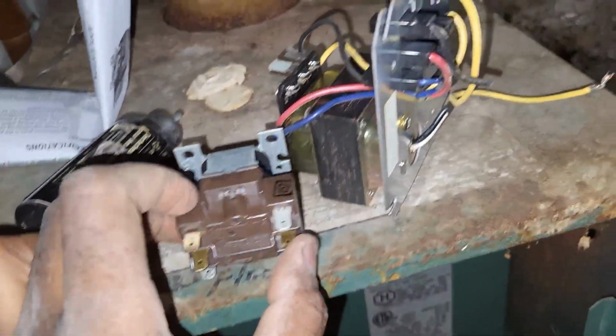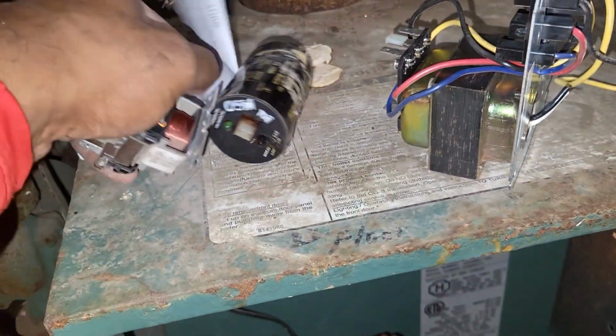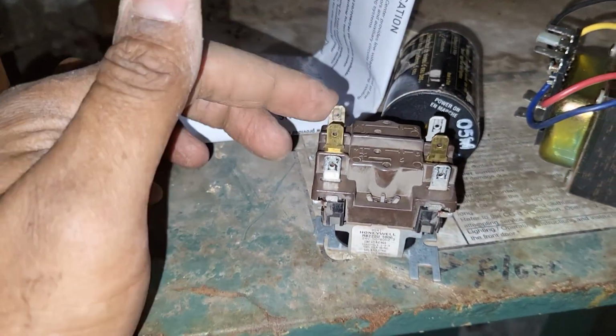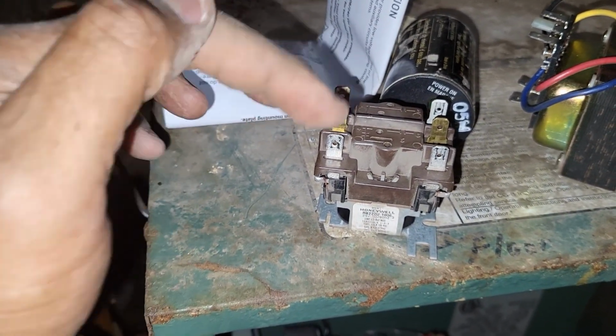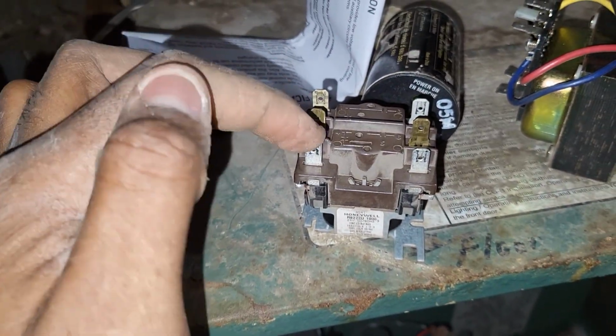issue. If we had a 115 volt issue, this would be on a totally separate side of the system. The only thing that's 115 volts on a residential gas boiler is our circulator pump. However, how 115 and 24 conflates is with our relay. This is a double pole, double throw relay, and the relay has 115 volts hot on one side, but it's not going to pass power from one side to another to feed the circulator pump until there's a call for heat.